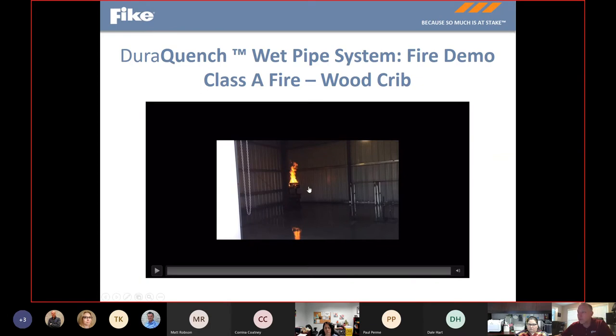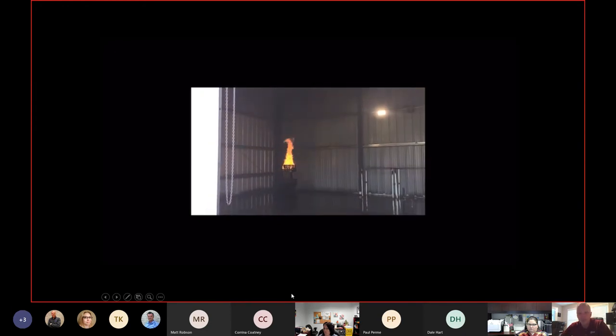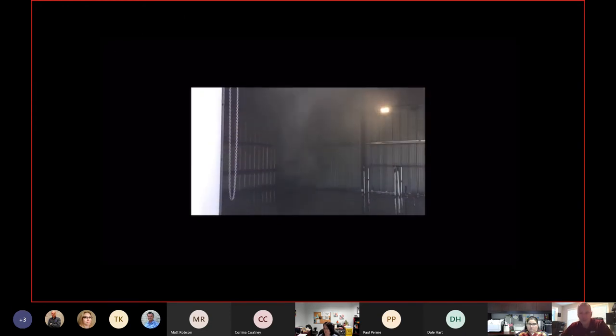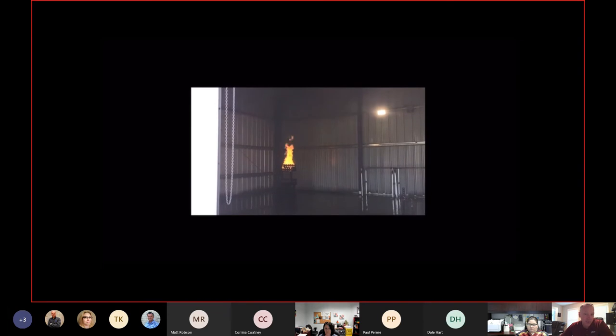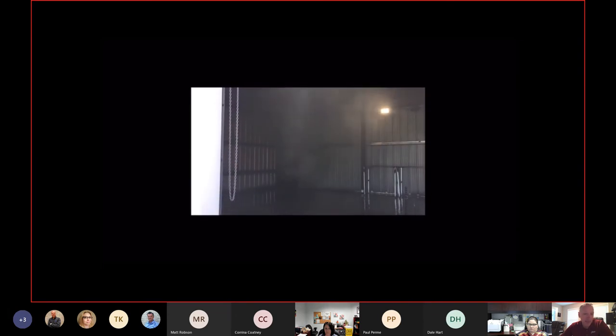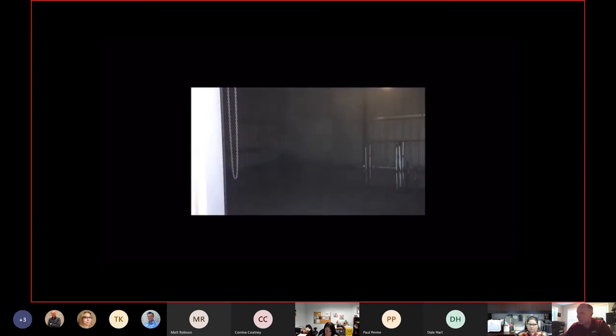And this video here will show you just how quickly one mist nozzle overhead will knock down and extinguish this large Class A fire. Before the cloud or the mist even seems to reach the fire, the flame is knocked down and extinguished very quickly. You can see some of the mist floats out the open doorway, but most of it stays entrained in the air inside the space where the fire was.